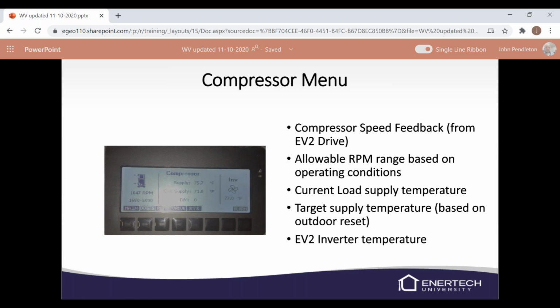If you press the comp button, it will take you to the compressor menu, and it will show your compressor feedback. So it'll show you what the RPM is, the allowable RPM range, the current load supply temperature, the target supply temperature, and it'll show your inverter temperature as well. And it'll animate if the fan on the inverter is on as well.